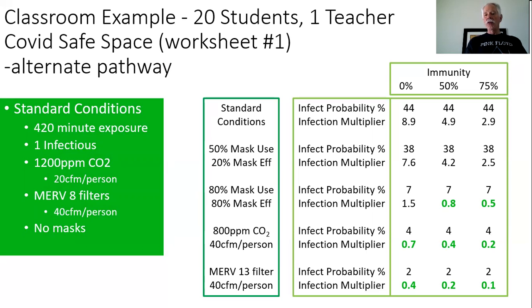And measuring the CO2 level is your key to knowing that that open window, that open door, or that increased opening on a damper has gotten that room or that space to 800 parts per million. You don't have to measure airflow, measure the carbon dioxide to see that you have sufficient fresh airflow, as shown in the calculator.